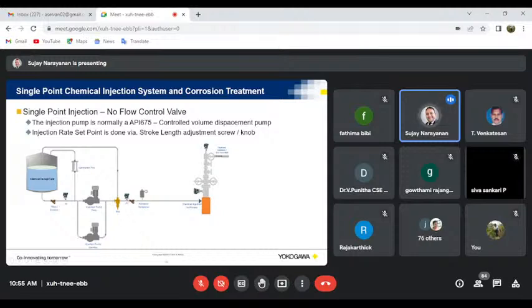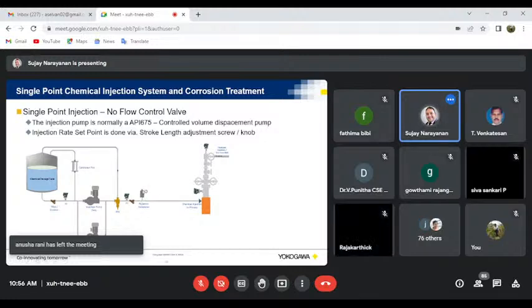Now after the pump we have something called, this is not required, I'm just telling you, a pressure relief valve. If there is any overpressure, this relieves the pressure back to the tank. Then you have the pressure gauge and a pulsation dampener. We have a pulsation dampener here because this pump works in strokes, on, off, on, off, like a pulse signal in electronics. During an off, you will not have flow. So the pulsation dampener acts like a capacitor and tries to give a smooth flow and not have these pulse signals.